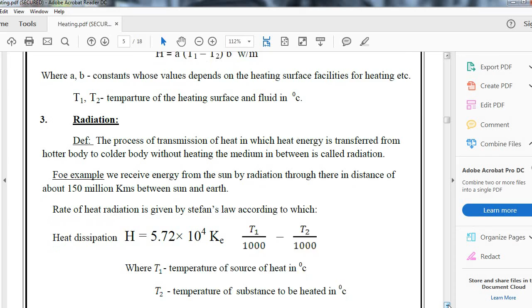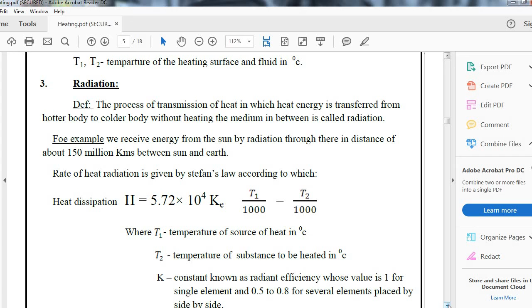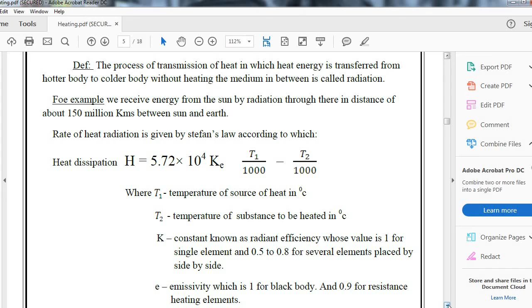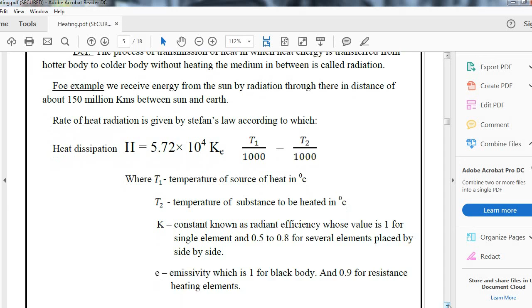The rate of heat of radiation is given by Stefan's law, according to which heat dissipation H equals 5.72 into 10 to the power minus 4 K E into ((T1 by 1000) to the power 4 minus (T2 by 1000) to the power 4), where T1 is the temperature of the source of heating in degrees Celsius, T2 is the temperature of the substance heated in degrees Celsius. K is a constant known as radiant efficiency, whose value is 1 for a single element and 0.5 to 0.8 for several elements placed side by side. E is the emissivity, which is 1 for a black body and 0.9 for a resistance element.